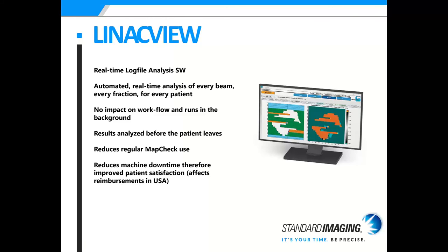LinacView is a real-time log file analysis software using fluence, making it super fast. It provides automated real-time analysis of every beam, for every fraction, for every patient with no impact on workflow — it runs in the background. If something isn't quite right, it sends an alert to the doctors or physicists for review before the patient leaves. It reduces regular MapCheck use and, in America especially, it reduces machine downtime by breaking down the linac log data into components — MLC, gantry, collimator, etc. — so issues can be addressed sooner.